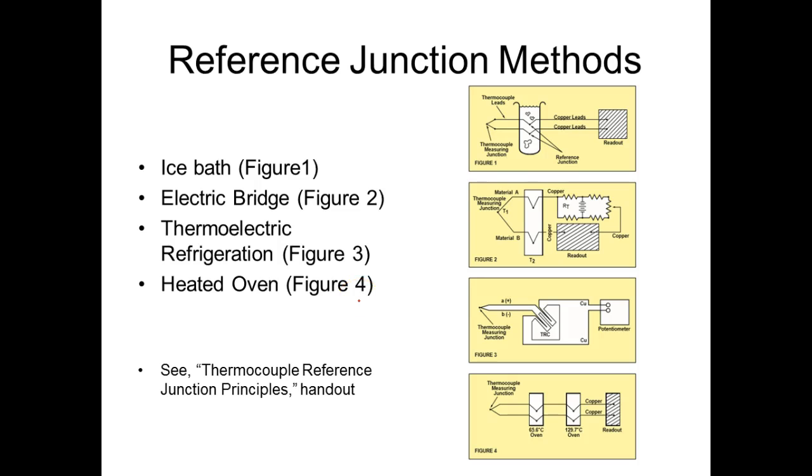So we can do this different ways. We can do it in what they call an ice bath, which is the way I worked. Or we can have an electronic bridge. We can use thermoelectric refrigeration and heat it up. All we have to do is maintain a precise temperature that we can reference the voltage of the thermocouple to. This is the one that's used most often inside the measuring instrument right here.